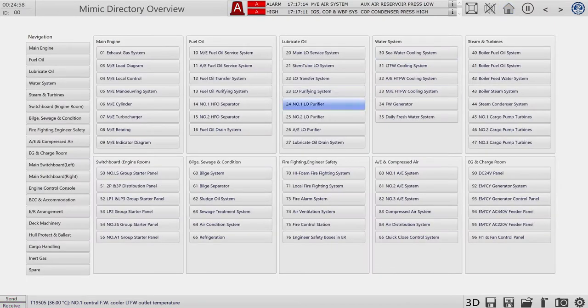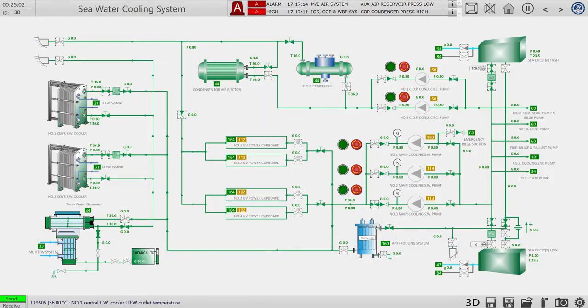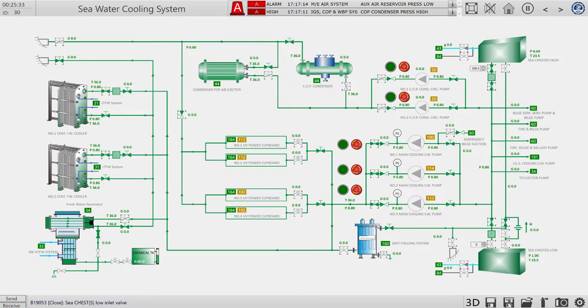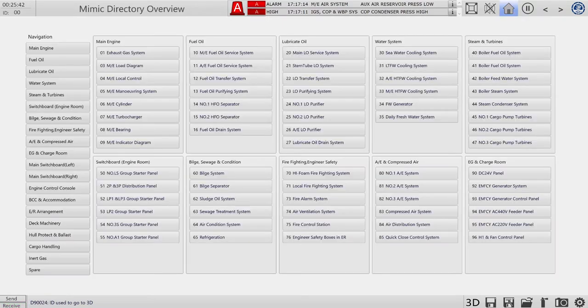Now let's check also the seawater system to see how the water enters through the pump. We will open the other pumps as well so it is not necessary to run up and down — they will be ready in case one pump trips. The next valve we will open is the overboard valve, so after cooling down the central coolers the water will be discharged overboard. This is how the seawater travels through the system.